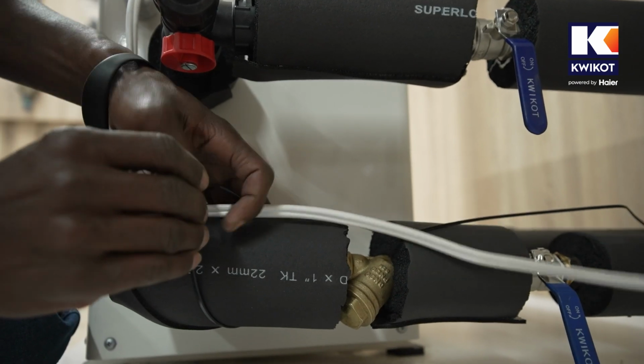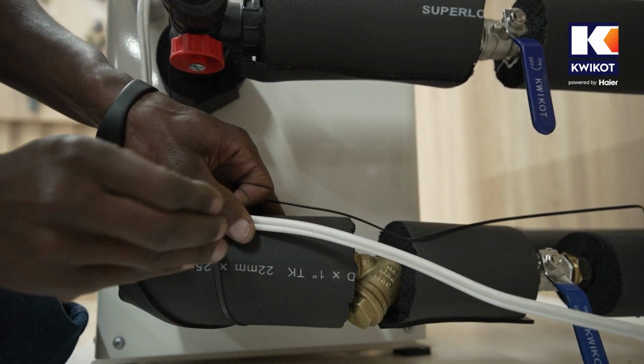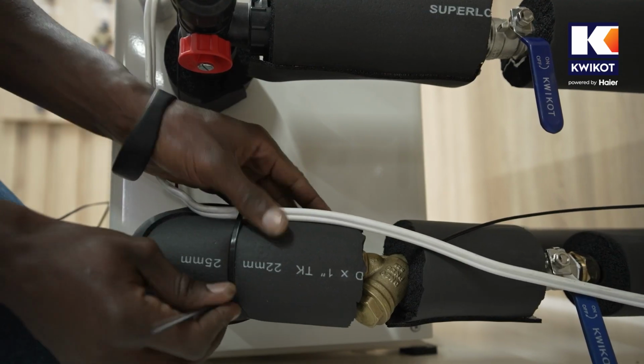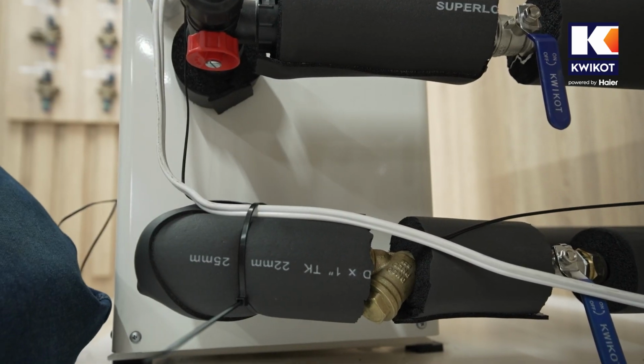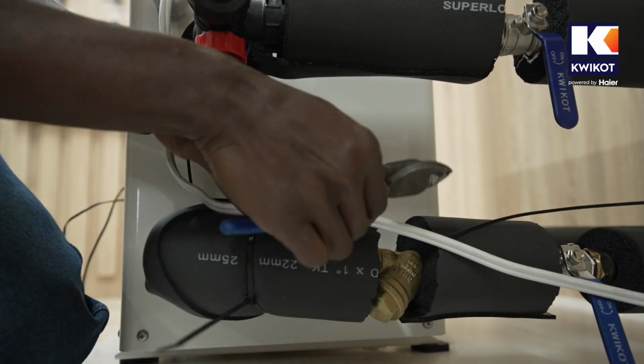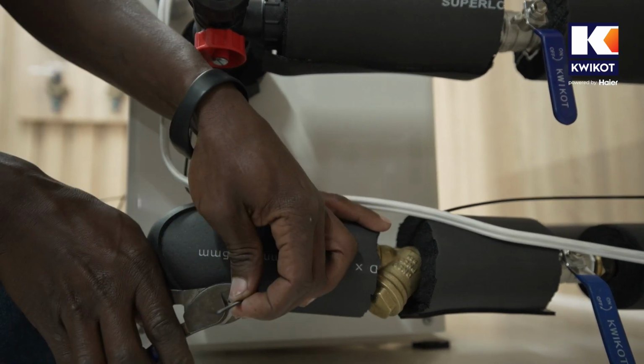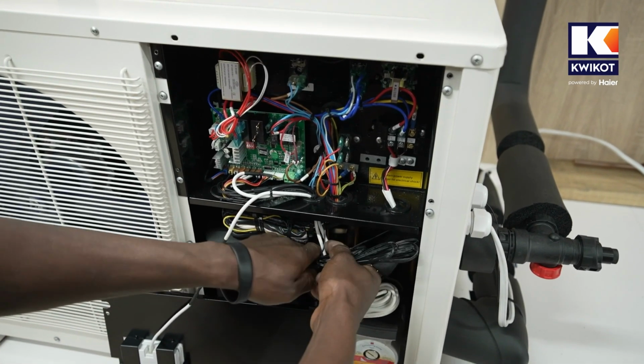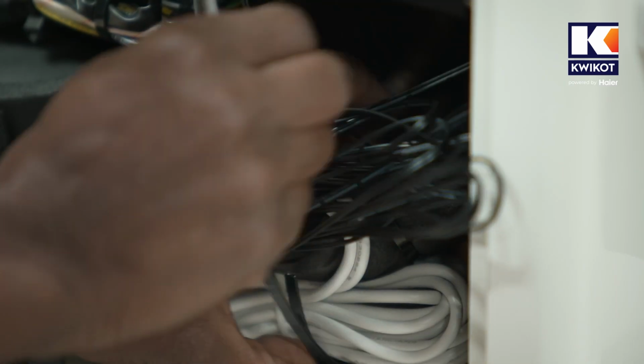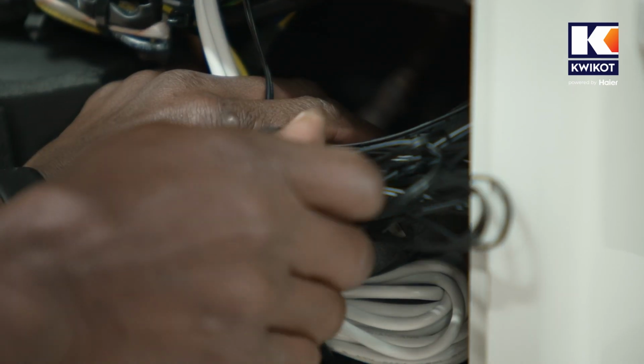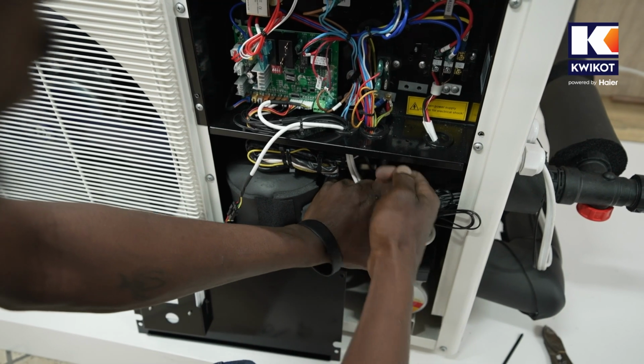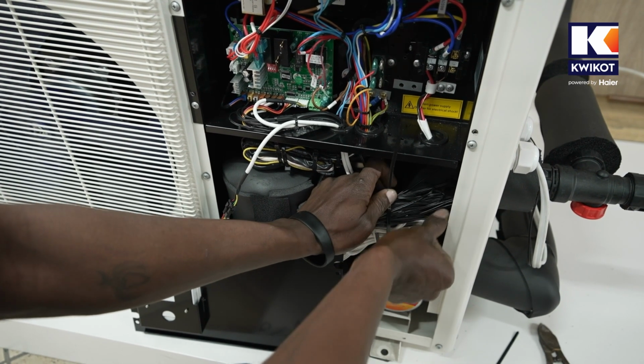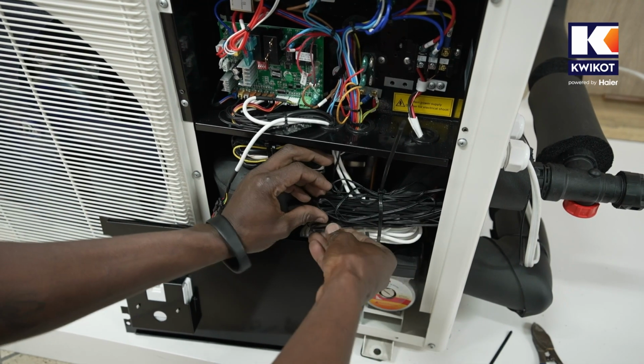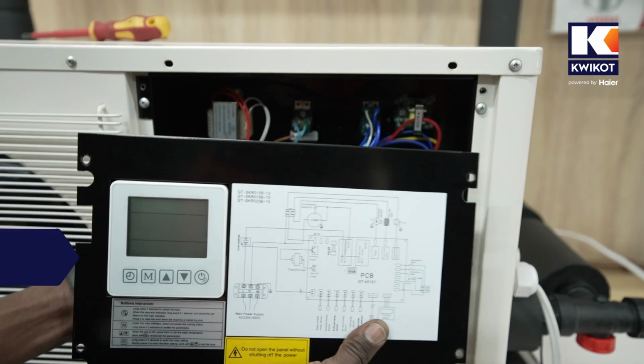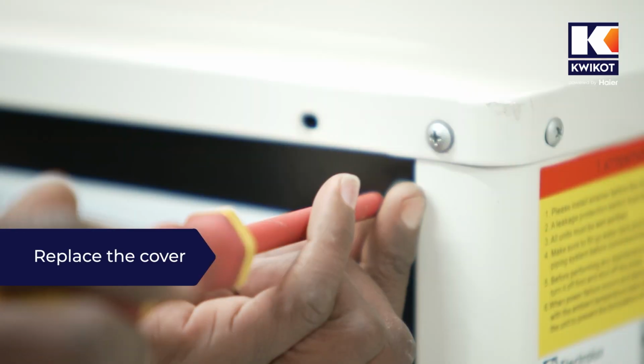So the electric cable needs to enter via the isolator that your electrician will install, and it should be positioned 1 meter away from the heat pump. This will allow you to isolate the heat pump if you need to work on it. Any excess cable can be placed back inside the box and then secured using the cable tie. If you need to move the cable tie from the machine, the white excess cable is about 5 meters long. And lastly, we can replace the cover.